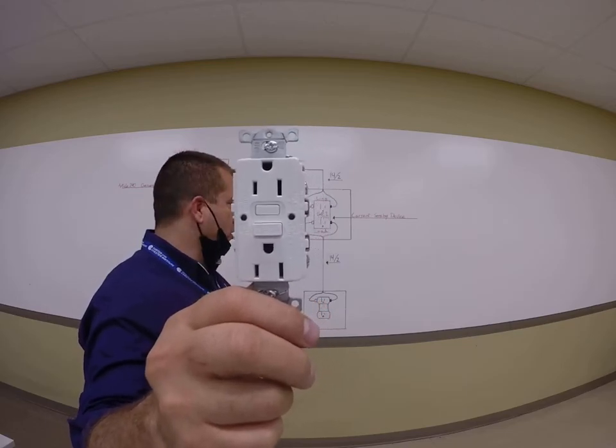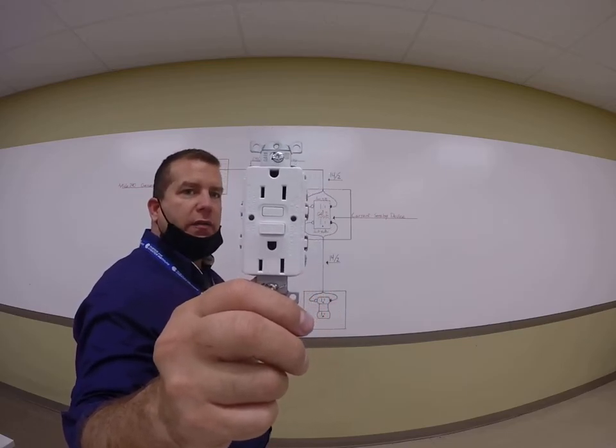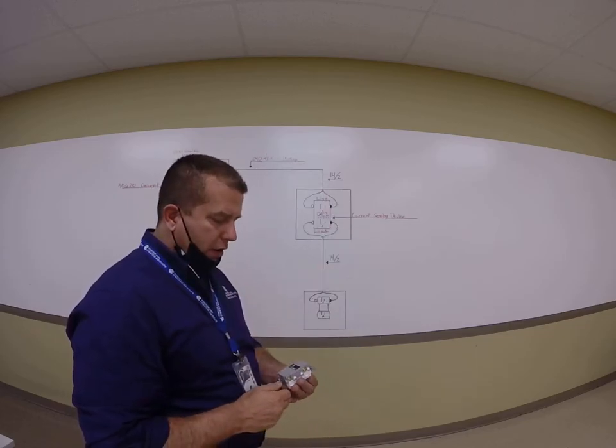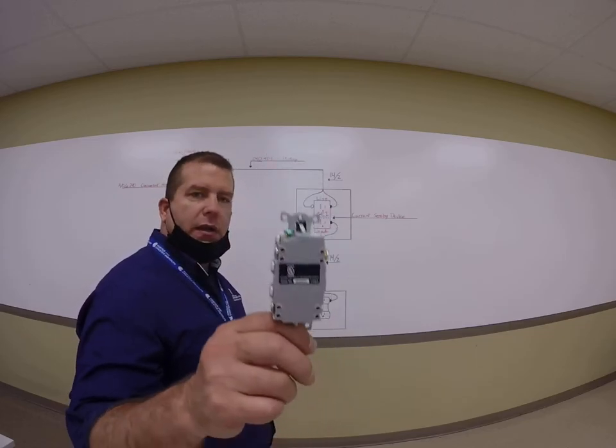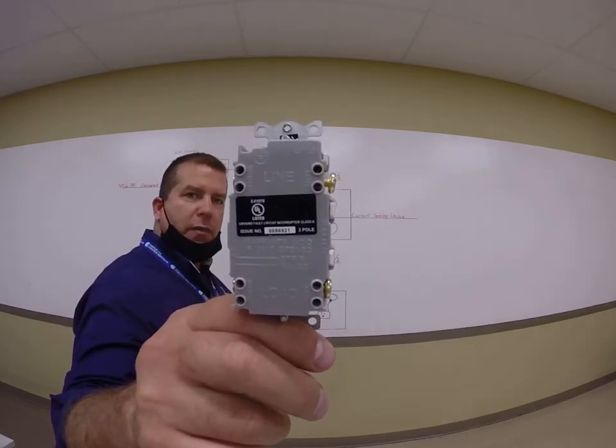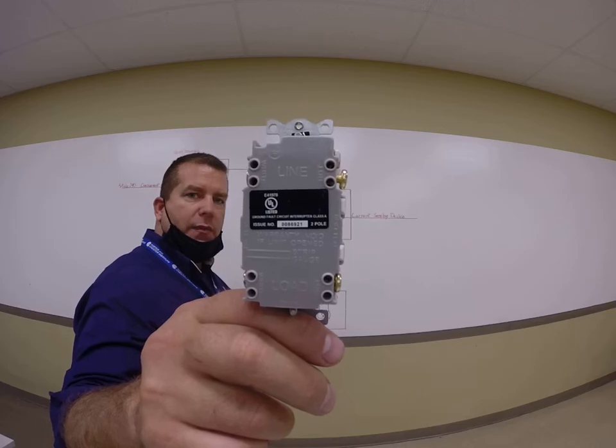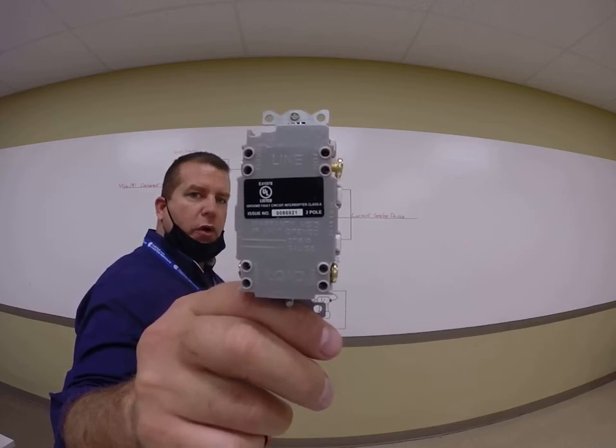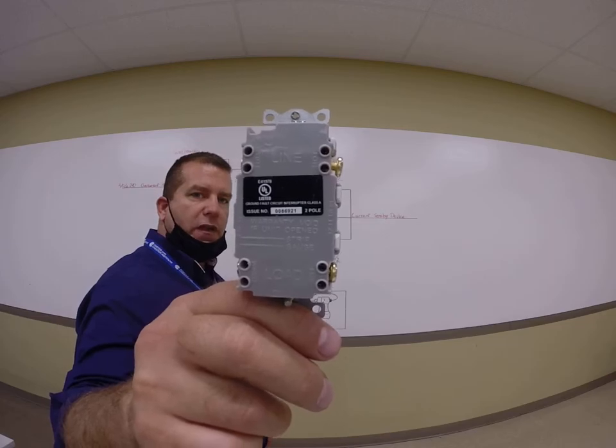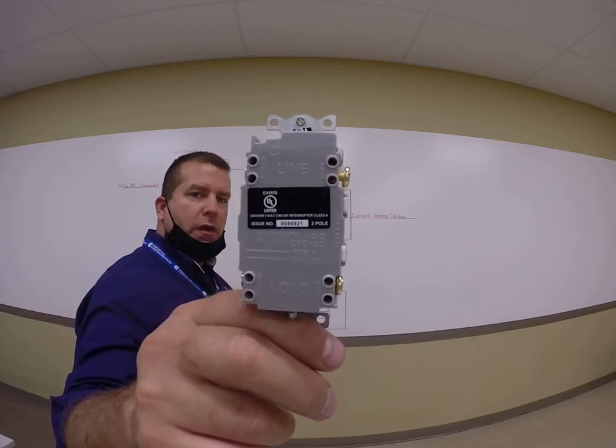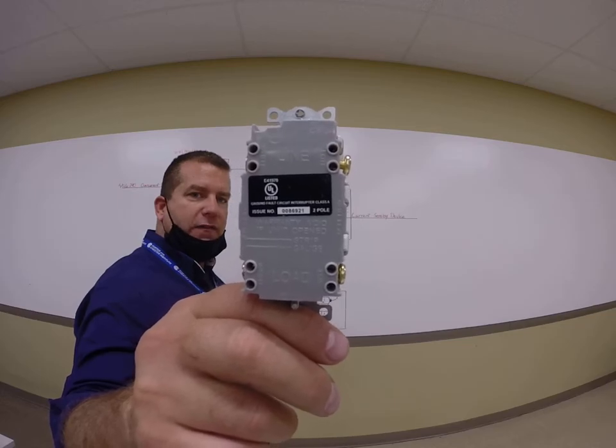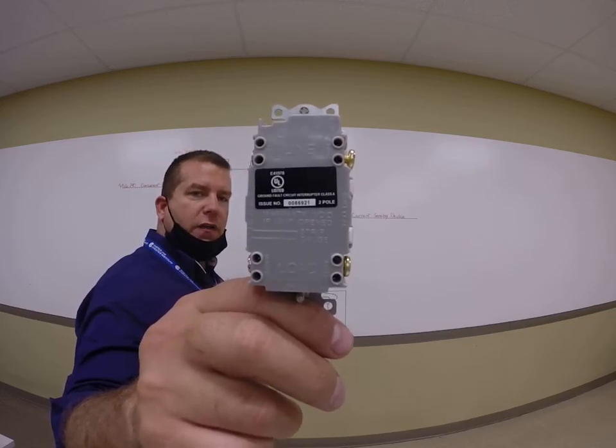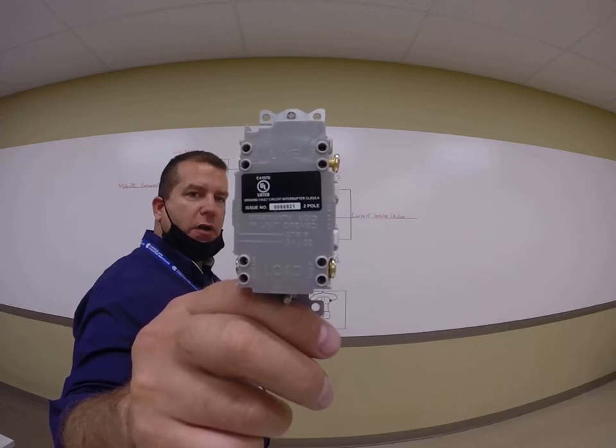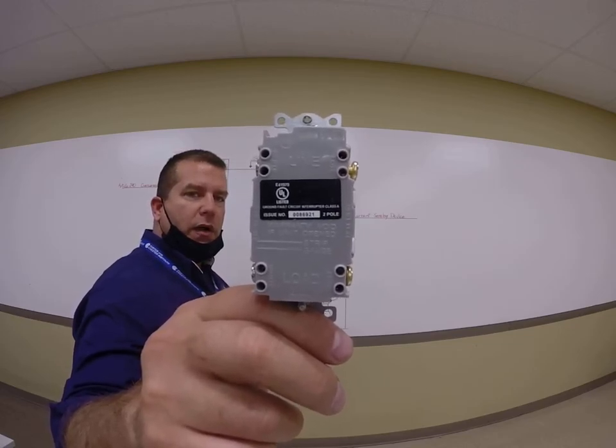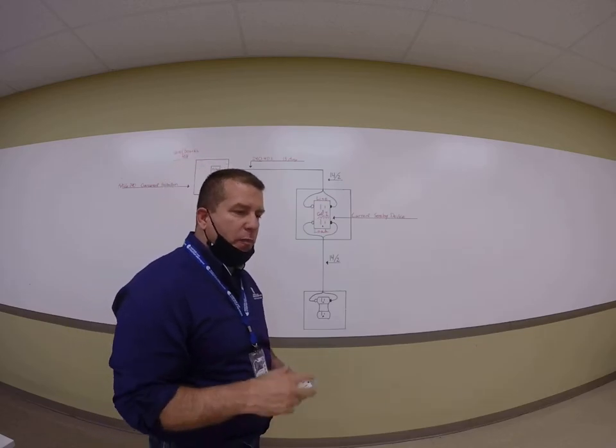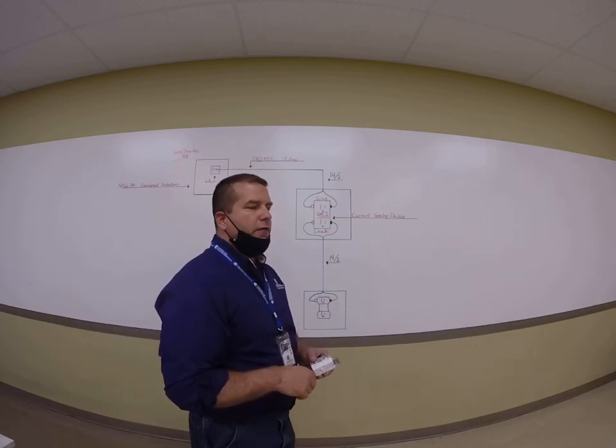So I'm telling you stuff you already know, but in addition to that, what I'd like to mention is for new guys, when they're installing them on the back, it says line and load. Now you may or may not be able to see that. Line means feed, load means what you're trying to protect with the ground fault circuit interrupter circuit. So it could be other receptacles that leave this box that are tied into the load that then become ground fault circuit interrupter protected.